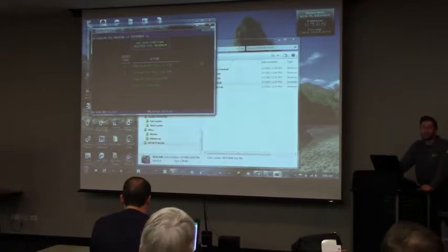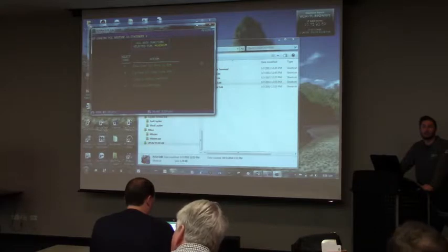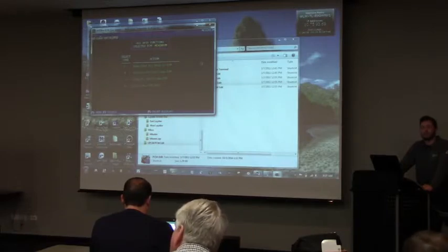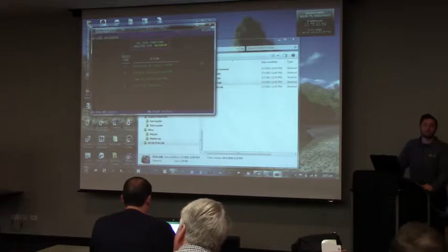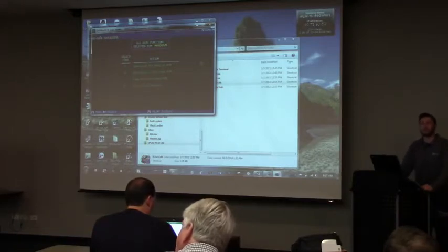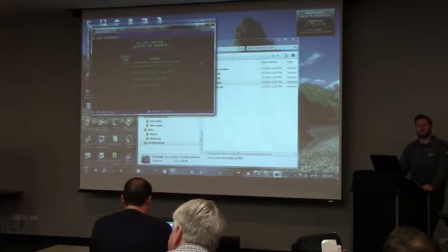And the other thing is all the logic is done with L for logical variables and R for real variables. And you only have 4 of each to use. So sometimes if you need more than 4 logical variables in a routine, you use them up at the top, and when you finish the logic with that, you reuse the variable again in the same routine, and it's actually a different variable at that point.